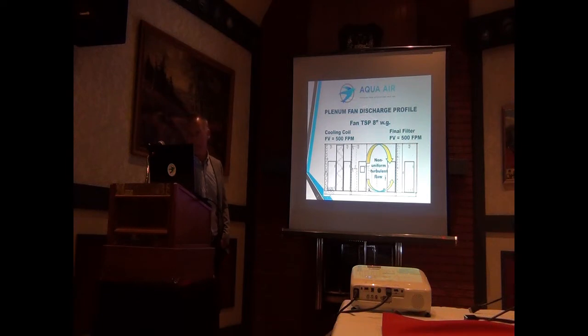But because this is swirling air, but it's moving much more uniform through these final filters, so you're going to get better loading on your filters. You may not get a 100% even throughout, but definitely better than if you saw that other profile. If you look downstream here, you've got the coil. Again, you're going to utilize maybe 70% of your coil. Maybe it's hard to calculate how much more effective it makes it, but you're going to be more effective because the profile as it comes off the coil, you're going to use more of that coil in that filter bank.